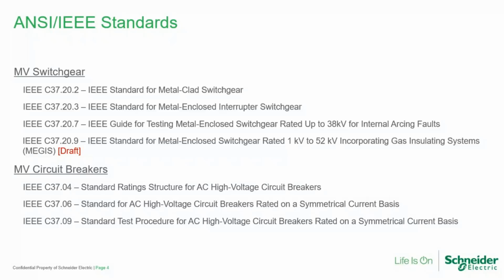So I think this is something that's often confused, but the important thing to know is if the term arc resistant is used according to an MV switchgear, then what they're saying is that they passed this test or they've tested according to this standard. And as usual in our industry, it's usually important to end users as well as local jurisdictions that it has a UL labeling that it was tested according to this standard in order to be called arc resistant.